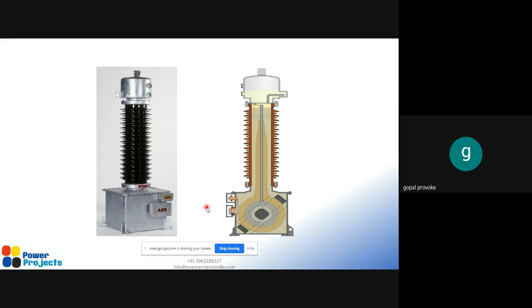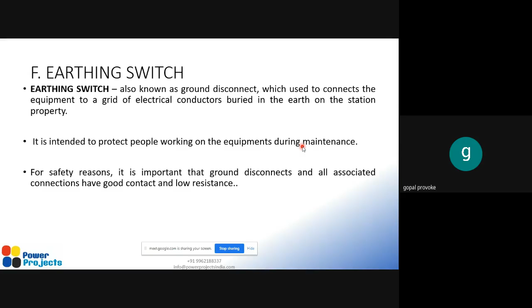And the earthing switch. We have an earthing switch for whenever we want to carry out maintenance of a substation. Any particular equipment which we want to maintain will be earthed. Since the substation will be in operation for a long time, due to induction and the spill, there will be residual flux stored in this particular equipment. So we earth that equipment in order to work on it safely. The main purpose of the earthing switch is to protect people working on the equipment during maintenance.